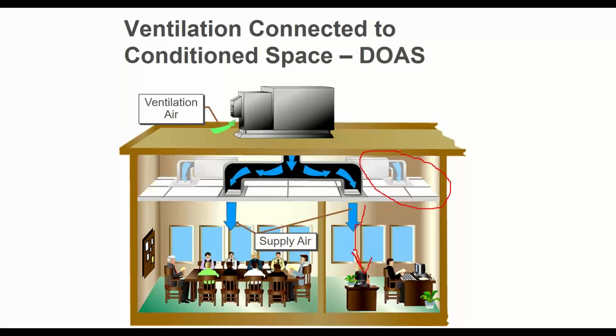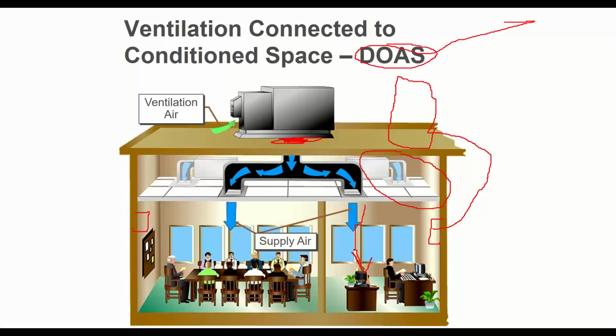The place this does happen seems to be if you're going to do mini splits on the wall, right? Or VRF, right? Mini splits and VRF, and those guys have their piping going up to their condensing unit, doing their thing. I might have to bring the outside air in like this. If I'm going to do that, I'm probably going to want to get an ERV that has heating and cooling in it as well, not just an ERV, right? And then in that case, it is no longer a standalone ERV. It is now called a dedicated outside air unit because I'll have to have heating and cooling in there to temper that back up to a more neutral 70, 75, or whatever it's going to be.